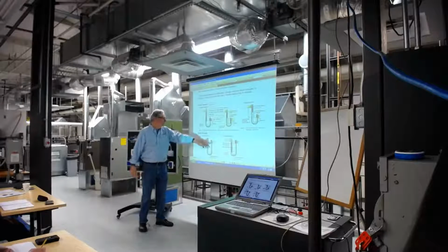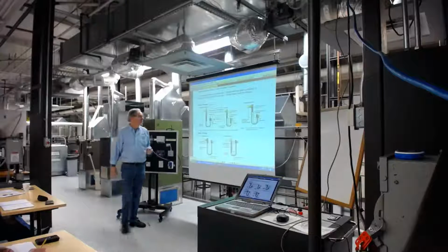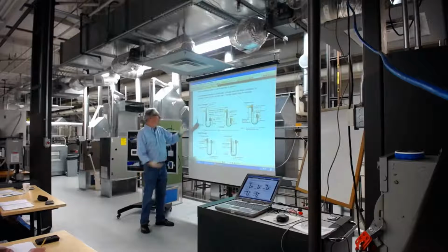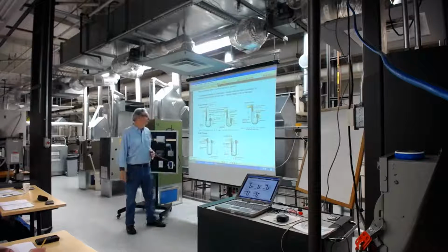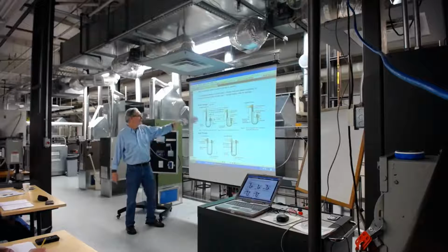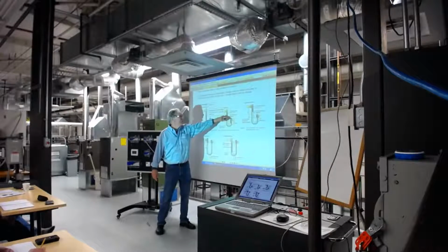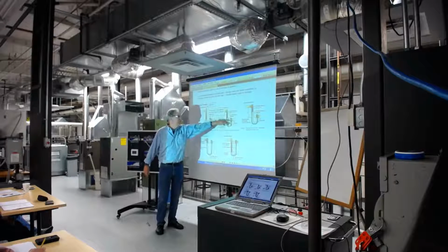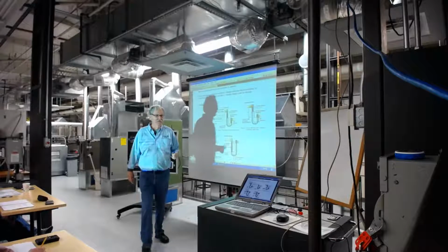And they're giving you the different measurements based upon the static pressure that's in that chamber. Okay. So if you have a draw through, which means you're on the suction side, this should be left open. The height from here to here is going to be based upon your static pressure. Okay. So they're just giving you, like over here, this height minimum. They're saying inlet pressure is 1 inch water column, and then they're going to have this to be half that amount at least. Okay. So these are the things you can check when you get out there, and you'll see them when we get out to the lab itself.